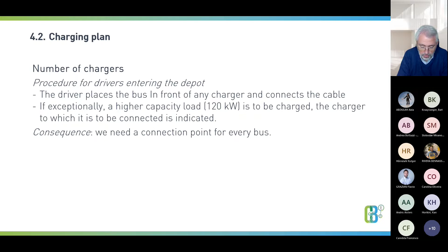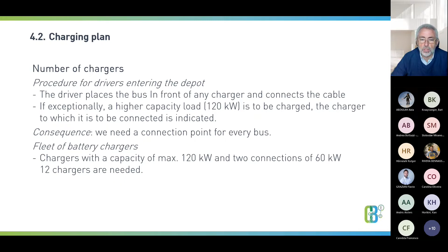It is possible to save on chargers, but then one has to disconnect buses and connect other buses on a regular basis, meaning moving buses during the day and night. The extra cost of chargers will compensate for the extra cost of staff to carry out these operations within a few years. Now, with a fleet of battery buses, the option we have for this operation is a charger with a maximum capacity of 120 kilowatts and 2 connections, so you can charge 2 buses at the same time at 60 kilowatts each, or charge one bus at 120 kilowatts on one connection. We will need 12 chargers to do that.